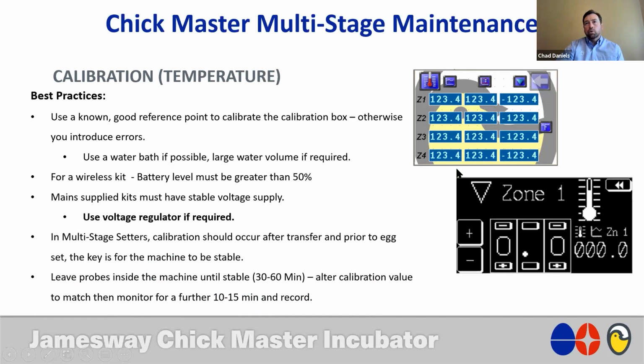Whether you have a Gen 4 or an older Gen 3 type system, calibration is pretty simple. But the key there is calibrate your calibrator, make sure that you are in a current state with your machine where you have a stable environment, and make sure the probes are left in the machine long enough to stabilize.